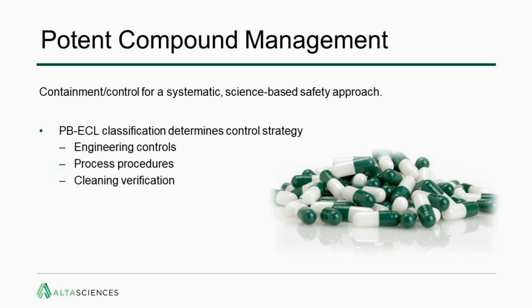Basically it increases the risk, so you have to be ten times lower for a classification of 4 than for a 1. A mathematician might tear that apart and say it's not statistically relevant, but the industry has found it and accepted it—and it definitely errs on the cautious side.